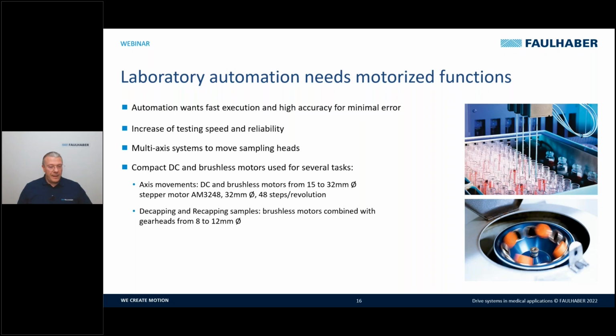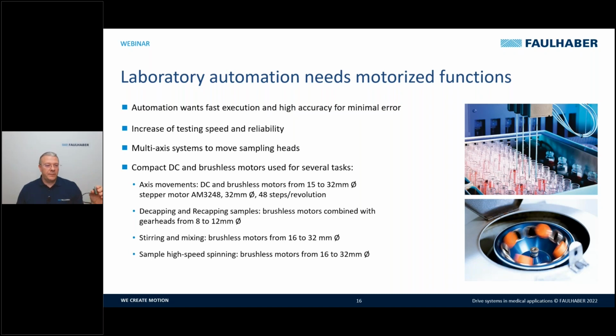For decapping and recapping samples, we can use a brushless motor like this, combined with a gearhead from 8 to 12 millimeter diameter. If we need stirring and mixing, we can use brushless motors from 16 to 32 millimeter diameter, or for high speed spinning, we may use a brushless motor like this, maybe a 2-pole brushless motor from 16 to 32 millimeter diameter.